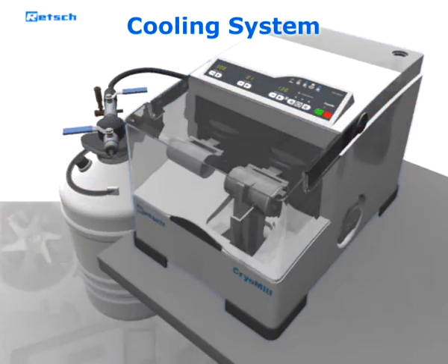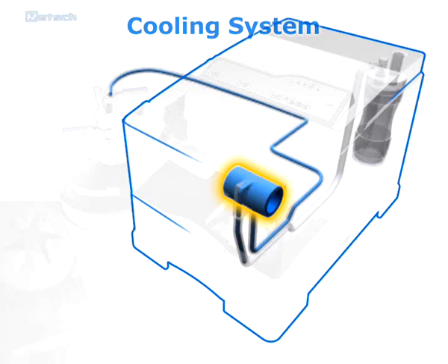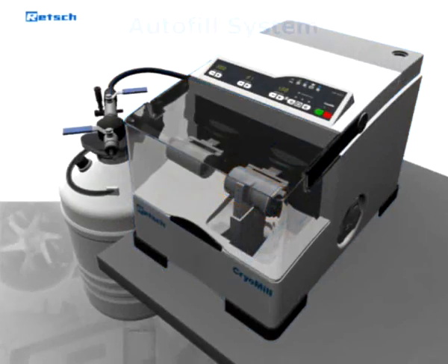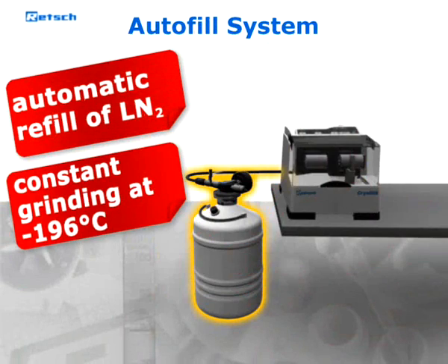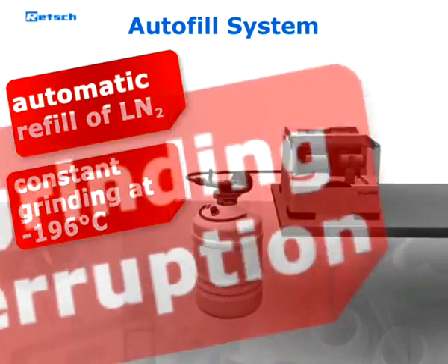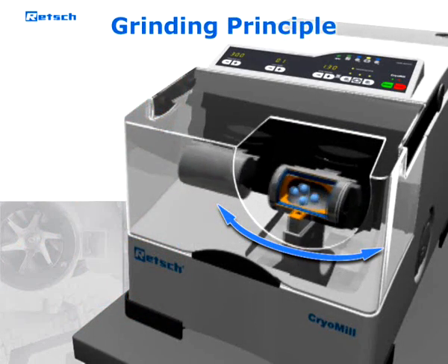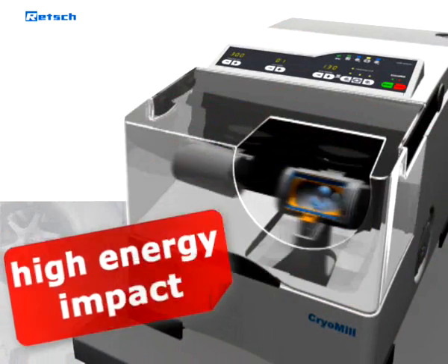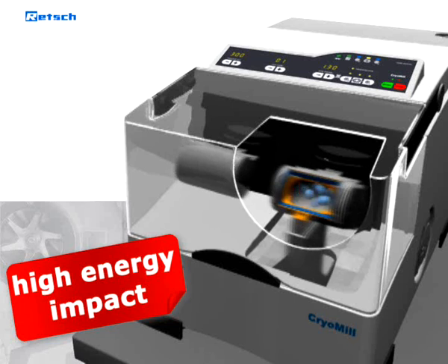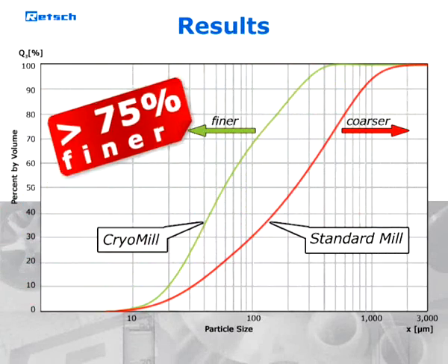After starting the machine, the liquid nitrogen circulates through the cooling system and embrittles the sample inside the grinding jar. Liquid nitrogen is continuously and automatically refilled from an autofill system in the exact amount which is required to keep the temperature at -196 degrees Celsius. An interruption of the grinding process is not necessary. The sample container performs radial oscillations in a horizontal position. Thus, the material is hit alternately from various sides by the grinding balls. This high impact and friction action, together with the sophisticated cooling system, makes the Retsch CryoMill much more efficient than conventional, non-continuous cryogenic grinders.